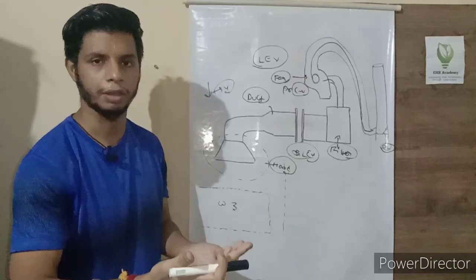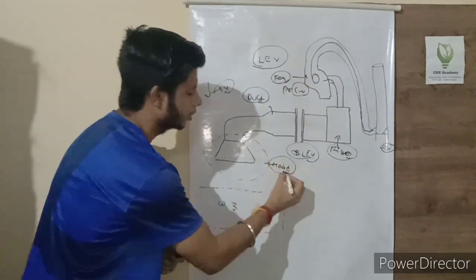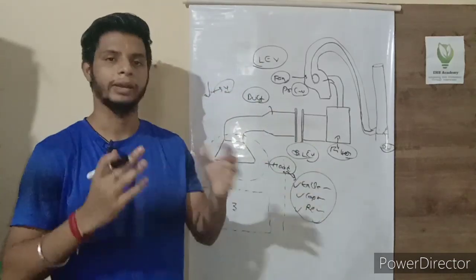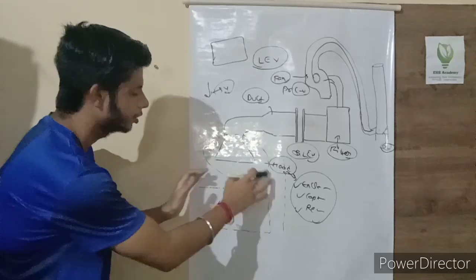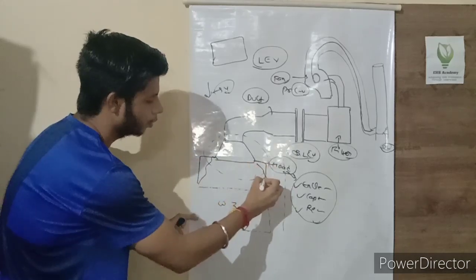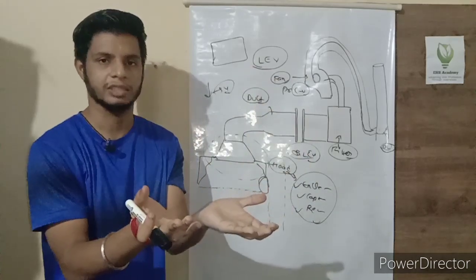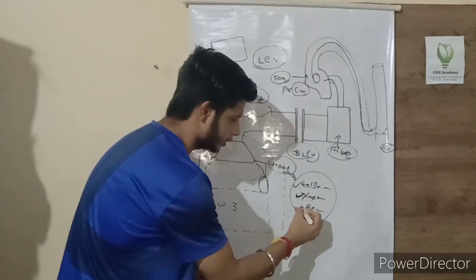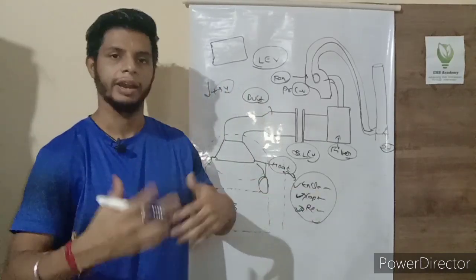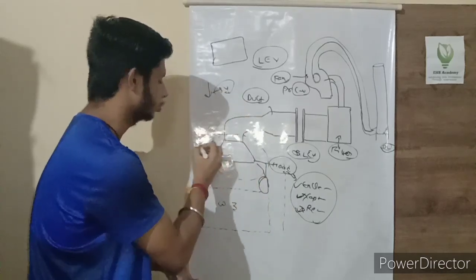Each part is crucial — if one part is not properly working or is damaged, it can affect the overall performance of the system. There are generally three types of hoods used in LEV: enclosing hood, capturing hood, and receiving hood. An enclosing hood is one in which the full work process is enclosed — covered from all sides — with only a limited opening for hands and visibility.